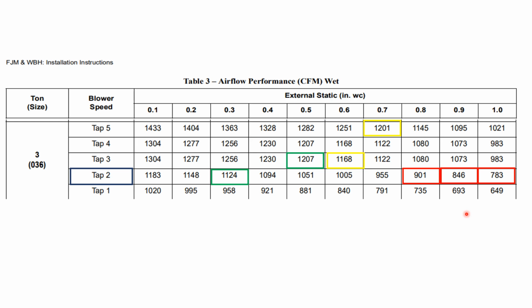Usually if you've got a bad compressor from the get-go, it's going to be DOA the minute you put power on it, or you're going to hear it coming apart on the very initial startup. If you've had it running for a week or two and then hear the noise, it's on your install, which means you've done something, whether it's airflow, whether it's line sets. We'll address that in other podcasts as well. But this one here is strictly our airflow capacity we're going to talk about.